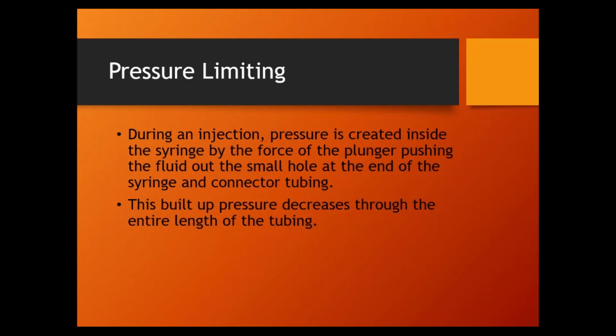Say we're shooting a flow rate of 10 milliliters per second, we hit our pressure limit, and it'll slow down to 9 milliliters per second. We might still get a good image. I mean, we might not. We may have to do it again anyway. But if the injector stops, we're definitely doing it again. So the machine will just slow the flow rate down, possibly salvaging this image. That's why we don't want it to stop.